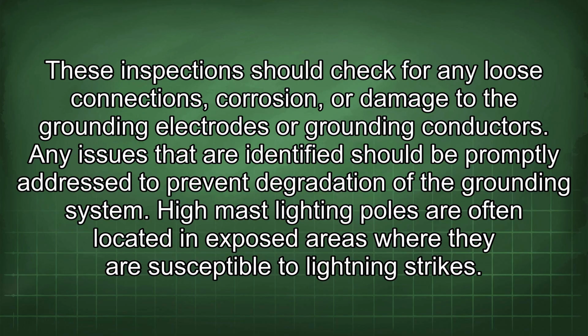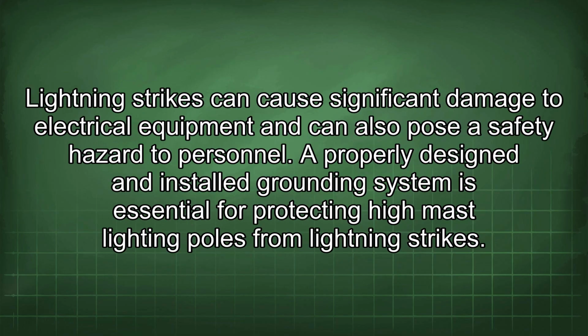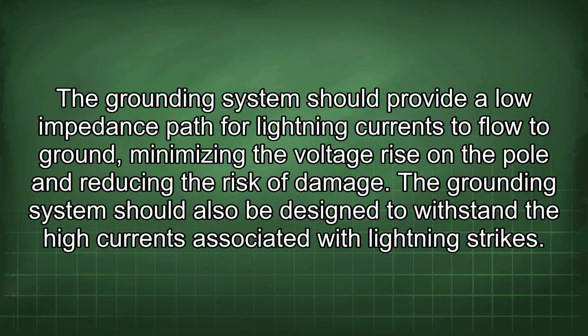High mast lighting poles are often located in exposed areas where they are susceptible to lightning strikes. Lightning strikes can cause significant damage to electrical equipment and can also pose a safety hazard to personnel. A properly designed and installed grounding system is essential for protecting high mast lighting poles from lightning strikes. The grounding system should provide a low impedance path for lightning currents to flow to ground, minimizing the voltage rise on the pole and reducing the risk of damage.